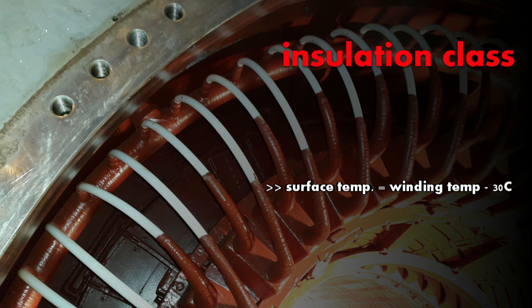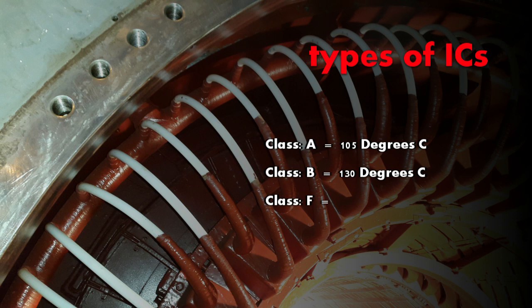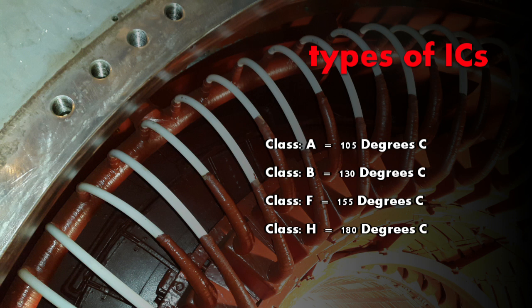Next comes the insulation class. The surface temperature of the motor is typically 30 degrees centigrade lower than its winding temperature. We have 4 different classes of insulation: Class A, Class B, Class F and Class H for motors. For Class A, maximum temperature rating is 105 degrees centigrade. For Class B, it is 130 degrees centigrade. For Class F, it is 155 degrees centigrade and for Class H, it is 180 degrees centigrade.